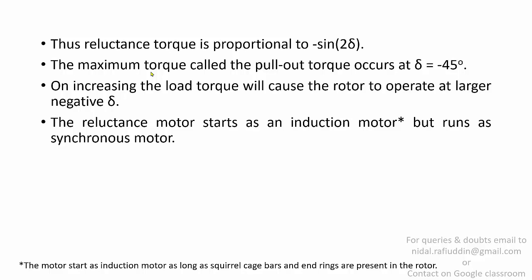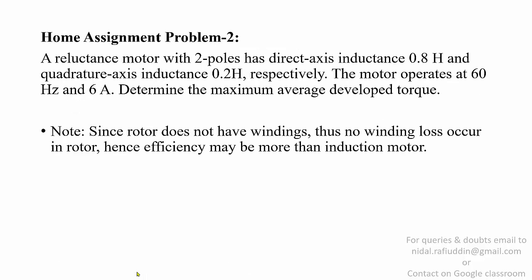The reluctance motor starts as an induction motor but runs as a synchronous motor. The motor starts as an induction motor as long as squirrel cage bars and end rings are present in the rotor — this applies to the synchronous reluctance motor. For the home assignment: a reluctance motor with two poles has direct-axis inductance Ld = 0.8 H and quadrature-axis inductance Lq = 0.2 H. The motor operates at 60 Hz and 6 A. Determine the maximum average developed torque. Note that since the rotor does not have windings, no winding loss occurs in the rotor, hence efficiency may be higher than that of an induction motor.